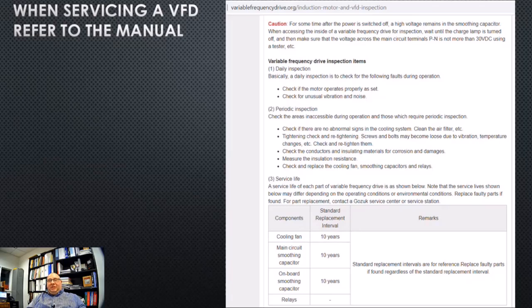VFD drives could be inspected, and there are some signs here or some checklists to go here. If you were servicing a VFD, they say in 10 years, change the cooling fan, the main circuit smoothing capacitor, onboard smoothing capacitor relays. What I do want you to take out of this is that if you have your paperwork and you're working on a VFD drive, don't set your paperwork and your manuals on top of the drive. What happens is the drive has a little vent on there, an exhaust fan, that uses ambient air to cool itself down internally. And a lot of times if you stick the manual on top of the drive, you block the airflow and then the drive is going to prematurely fail.